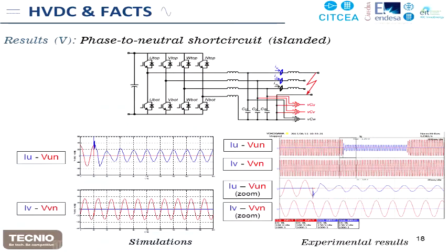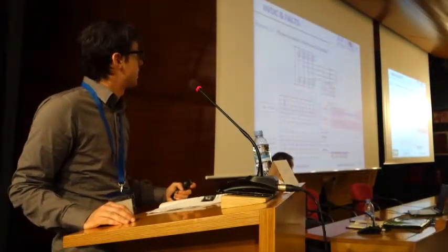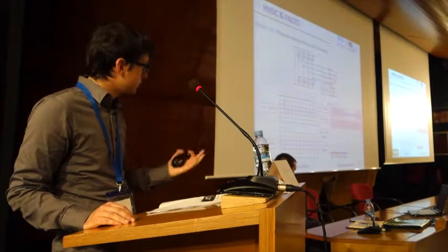Obviously, if you see the blue line here, you can see that there is an overcurrent that is related to the non-controllable time. This means the system implicitly has a switching frequency, a switching period. So between the moment the fault occurs and the first time that the control knows that it has to react, the current is not controlled. And this is the reason why we have here a peak of 2 times the maximum current that will be supported by the short circuit algorithm. But after no more than 2 grid cycles, the system is able to deliver a sinusoidal waveform current supporting the short circuit.